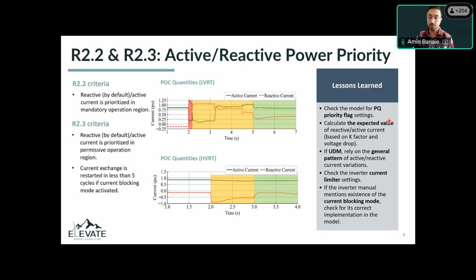That might be available in the UDMs as well. That can give you an idea of what the inverters are operating, which PQ mode they're operating in, and then calculate the expected value of reactive current or active current. As an example, if the inverter is following K-factor diagram, you can calculate reactive current by multiplying K-factor by the voltage drop and see if that entire capacity is allocated to reactive current. So that's going to be reactive current priority mode. If reactive current is curtailed to some value below that value, then that's not a reactive current priority mode.